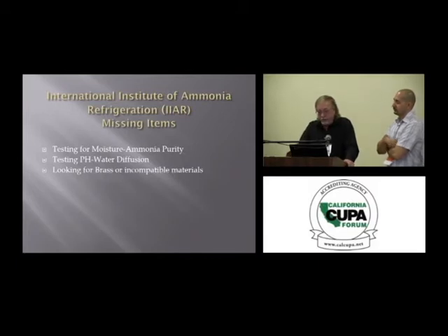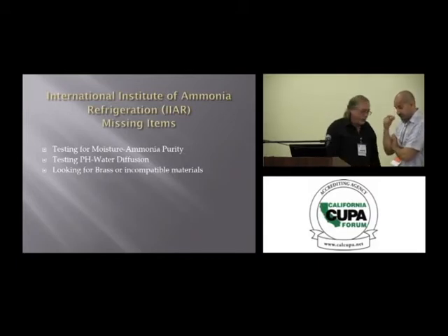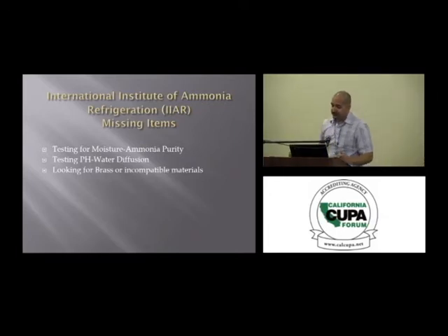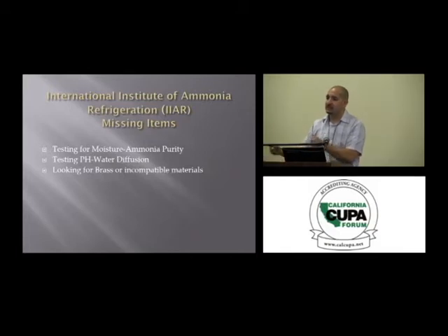Some things that the IIAR bulletins don't cover are these three items here. Testing for moisture, ammonia purity. There was a facility that, as far as they thought, was cutting back on cost. One facility was using farming ammonia, which carries a lot of water. After we did a PHA and an MI inspection, we talked about what they would do: they would bring in farming tanks and transfer ammonia themselves. They had no training, no PPE, and I made the recommendation, how about get properly trained or just get away from using farming ammonia.